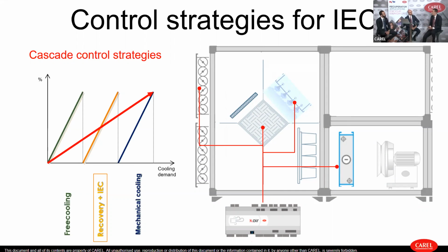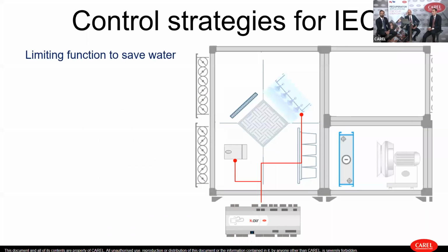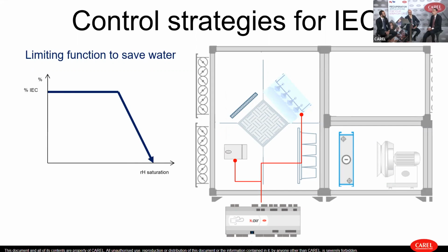This is a saving, a benefit that we can get in terms of energy consumption, but we would also like to get additional benefits from the integration between the controller, the humidification system, and the heat recovery system. And also we would like to preserve water during the indirect evaporative cooling. In this sense, we are able to control the indirect evaporative cooling system by controlling the humidity on the exhaust air. This means that we can get the maximum effect possible in terms of indirect evaporative cooling, because if we are close to the saturation point on the exhaust air, we can reduce the power of indirect evaporative cooling because we cannot get more efficiency than the one we are getting at that moment. So this kind of control strategy put together permits us to save energy, but at the same time also save water in this particular kind of application.